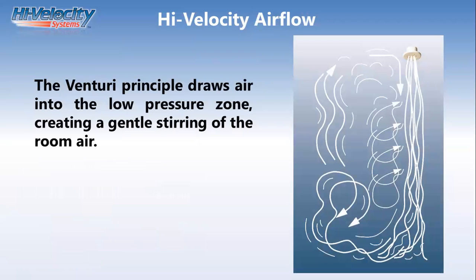So as that air is coming out at about 1,200 feet per minute, it creates a low pressure zone 360 degrees around that outlet. That low pressure zone is going to grab that still stagnant room air and pull it into its airstream, forcing total circulation from floor to ceiling. Even with the absence of a return air in a room, we will mix and move that entire room air, where with conventional forced air, you spill it out of one side of the room and have a return air on the other side of the room in the hopes that that draw from the return will be forcing that mixed heated cooled BTUs to the space.